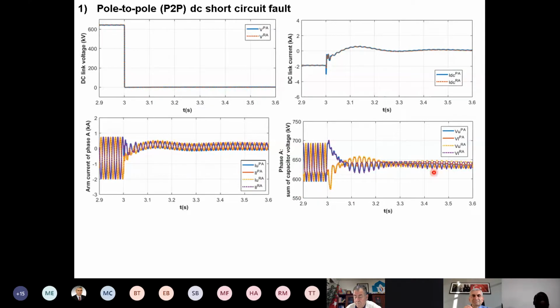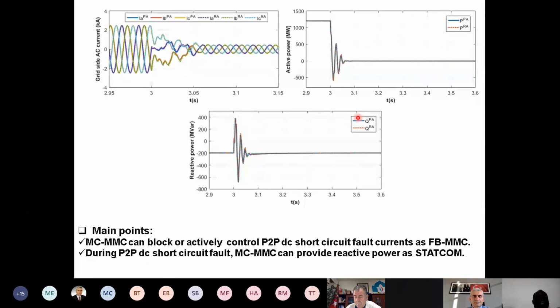And you can see here, even though the DC voltage was collapsed to 0, we can still control reactive power at the rated value, with a brief disturbance just around the instant of the fault. The active power dropped to 0 because the DC voltage dropped to 0, and VDC times IDC equals DC power equals active power. Since the VDC dropped to 0, the active power has to go to 0.